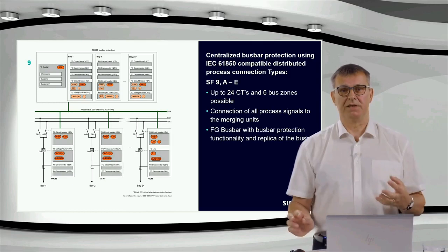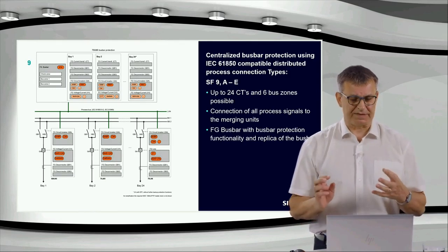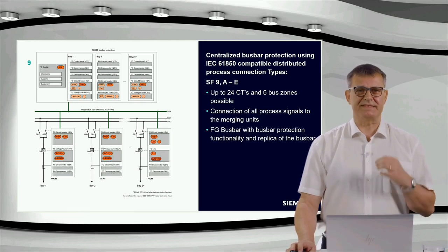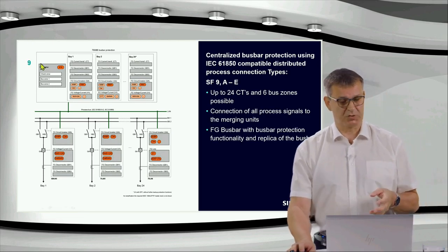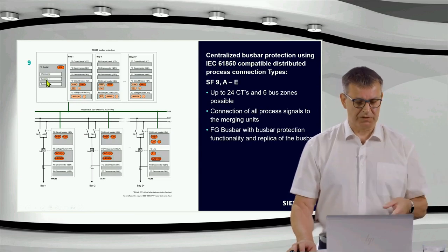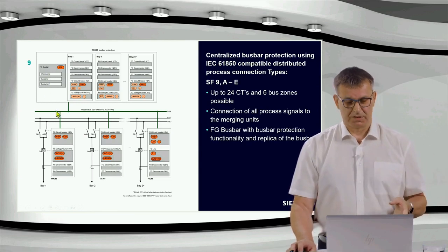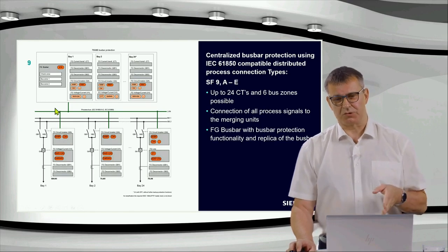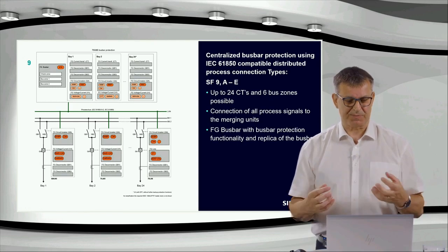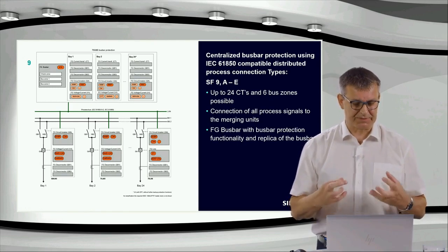Essential, as it is absolutely the same device, we are using absolutely the same algorithms. We have the same function group busbar with a function block check zone, with a function group bus zone 1 for bus zone 1, and so on. So you can absolutely trust also the tests you have done with the centralized busbar protection, because it's really the same type.